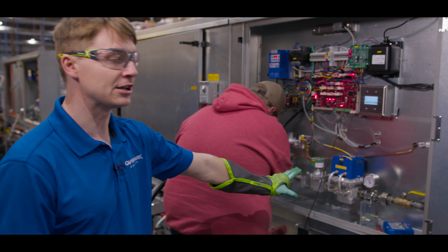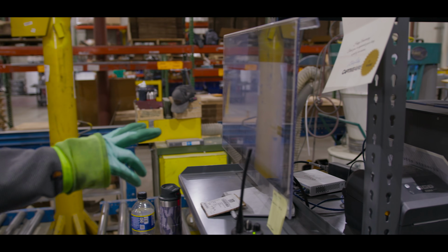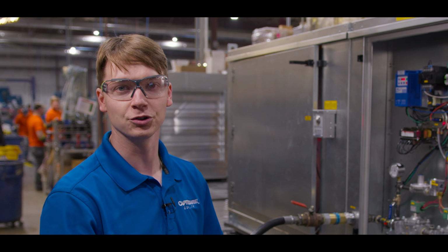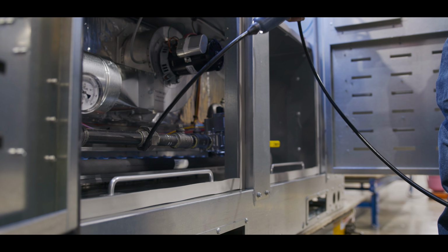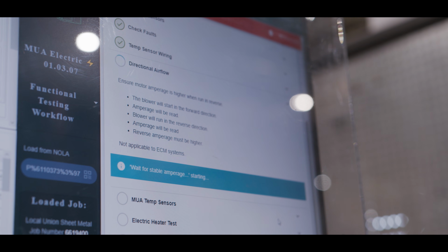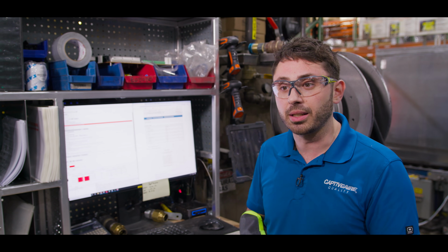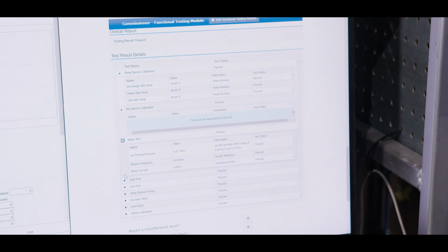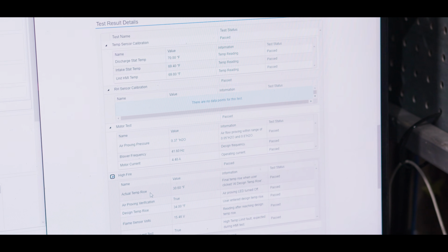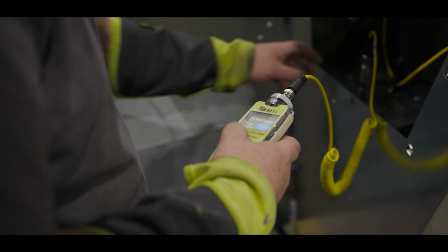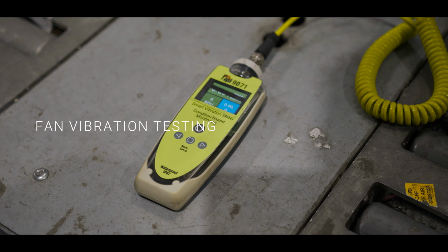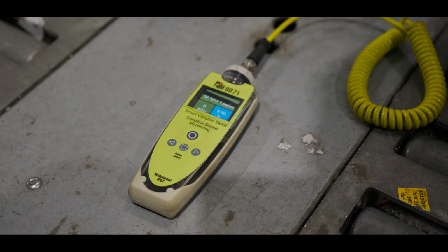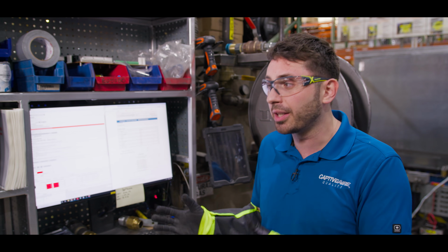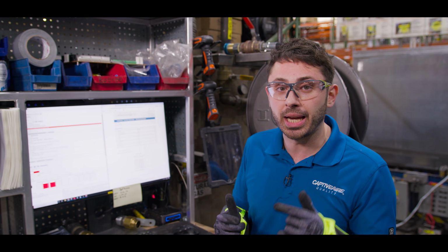You can see him going through and he was just measuring for leaks while it's prompting him on the screen to check for leaks. So it's not just software automated testing, but we're also having the manual user secondary verify without adding any extra time. We 100% functional test our unit. So part of this automated testing requirement was, let's grab all that data, all that metadata, and upload it to our quality control module. And furthermore, let's make that accessible to tech support, to sales regions. So if there is an issue in the field, maybe associated with the install or application or something else, we'll be able to reference how that exact unit tested within our facility.